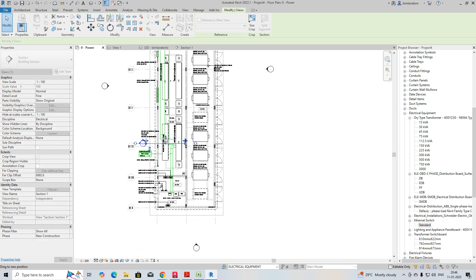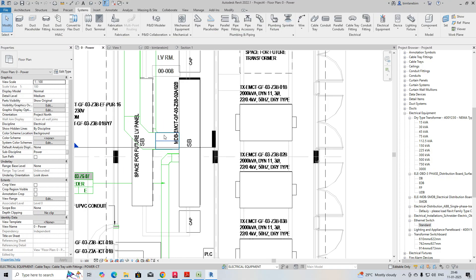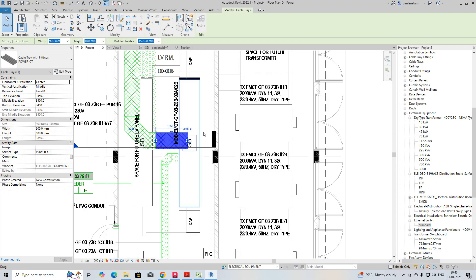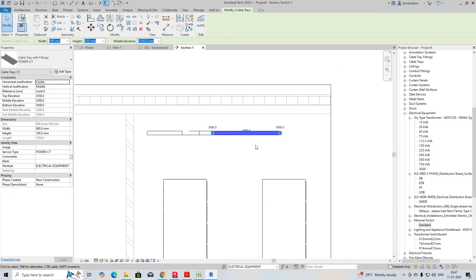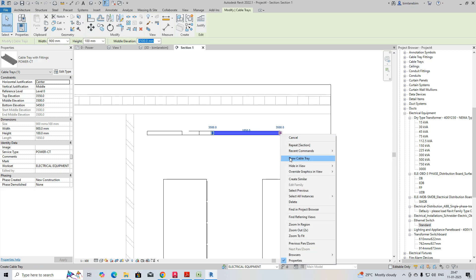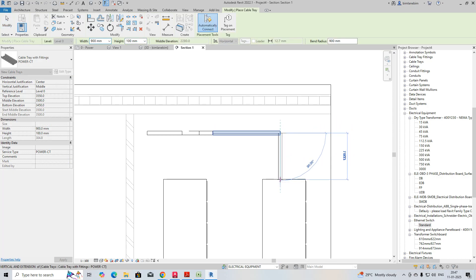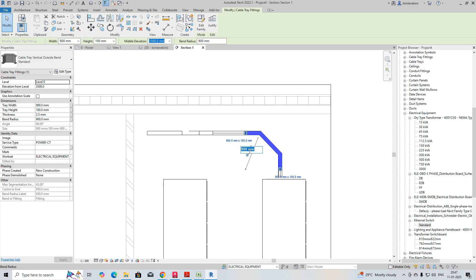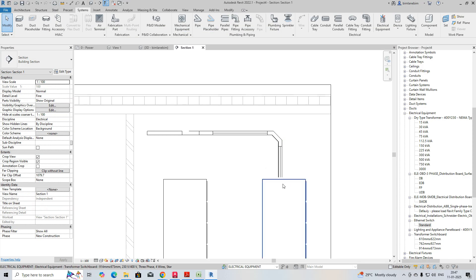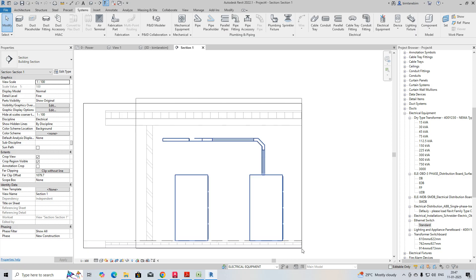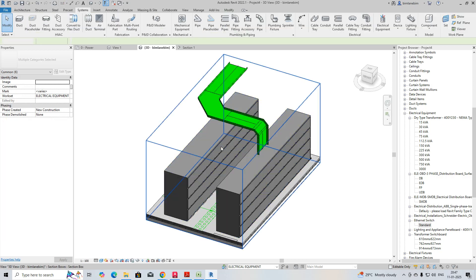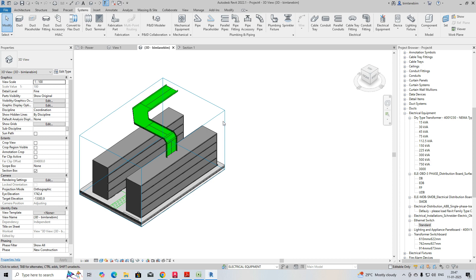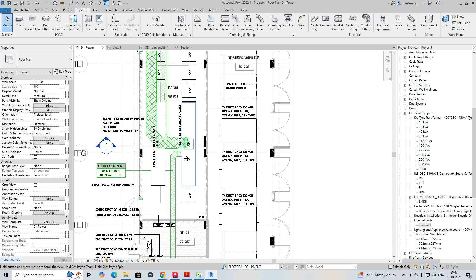Stretch the section view near to the cable tray. In the section, draw the cable tray and drop it down to the panel. If you want to reduce the bend radius, you can set it to 300mm or whatever size is required depending on the cable size. In the 3D view, you can see it drops into the panel.